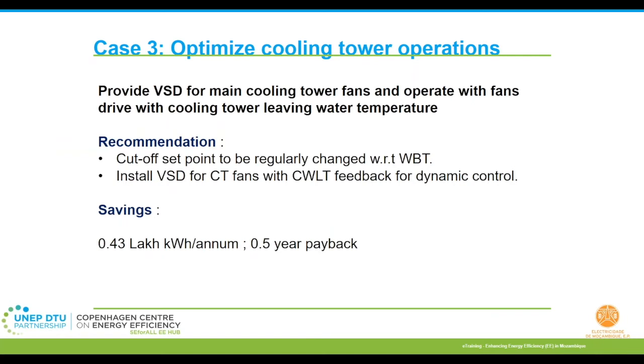So we have recommended to change the set points regularly with respect to the ambient wet bulb temperatures, and also install a variable frequency drive for the cooling tower fan motors, with cooling water leaving temperature feedback. This way it is not an on and off operation, but the drive regulates the frequency and the power consumption as per the water temperature requirements. For example, if my set point is 26 degrees and my cooling water temperature is now 28 degrees, then the fan drive would be operating at full speed to help me achieve that 26 degrees centigrade.